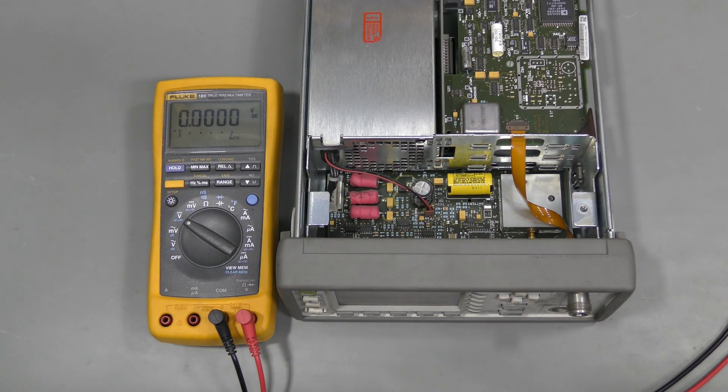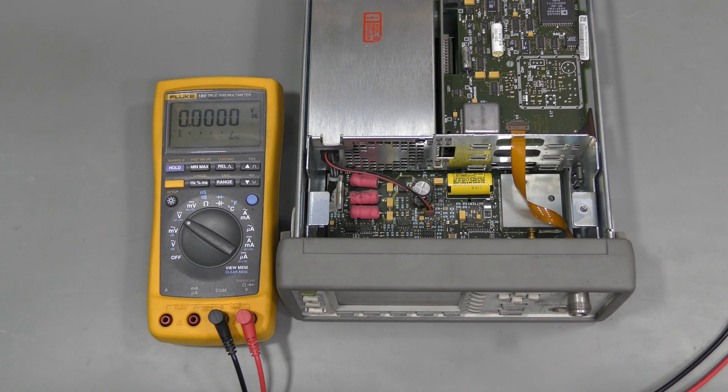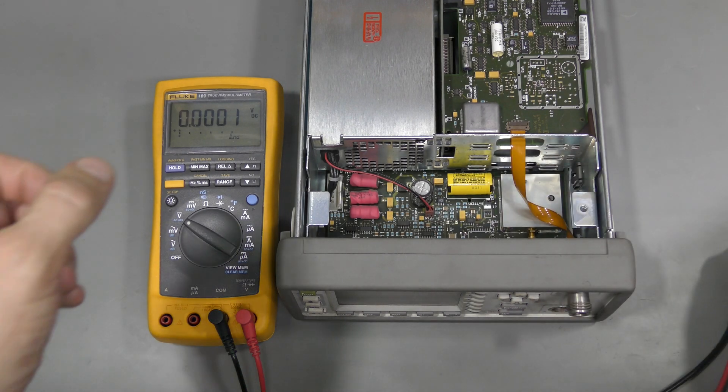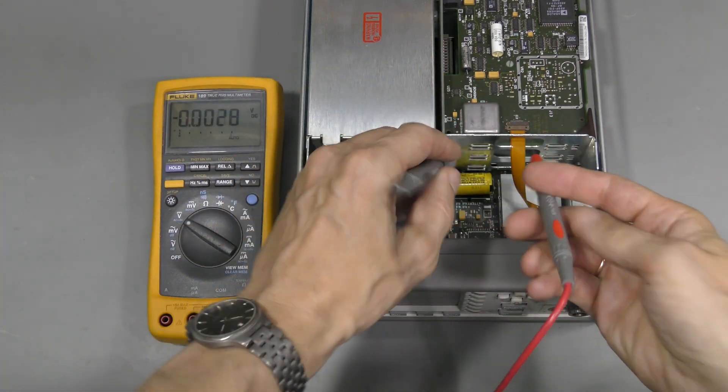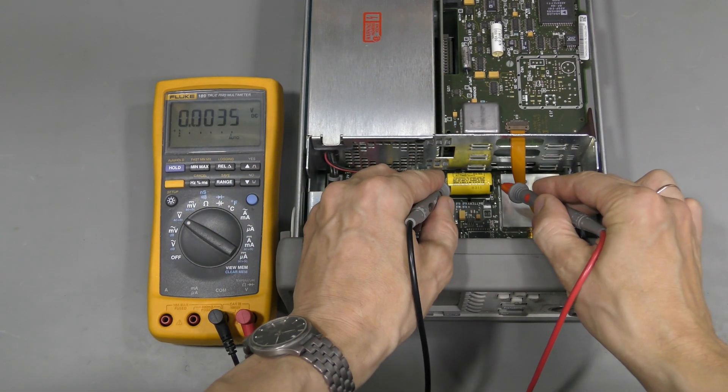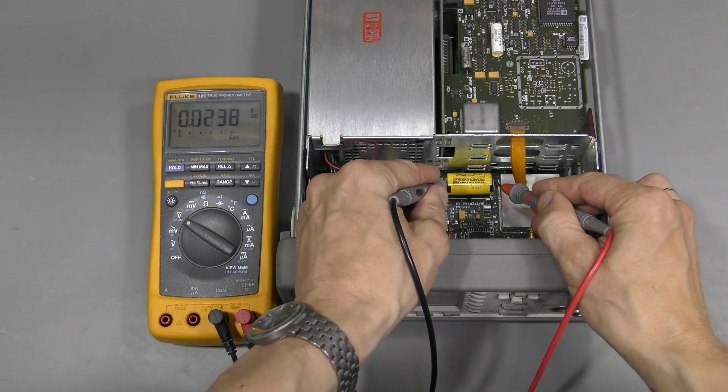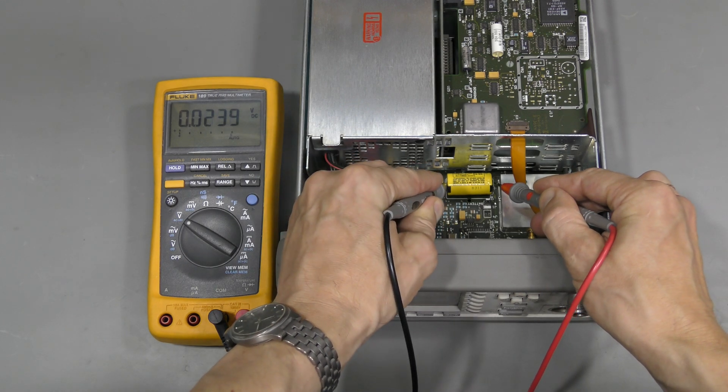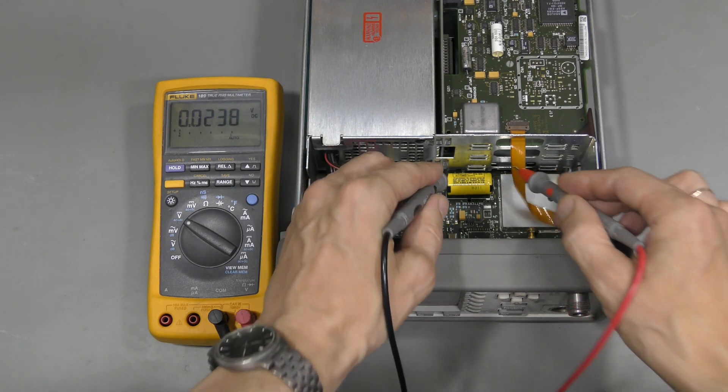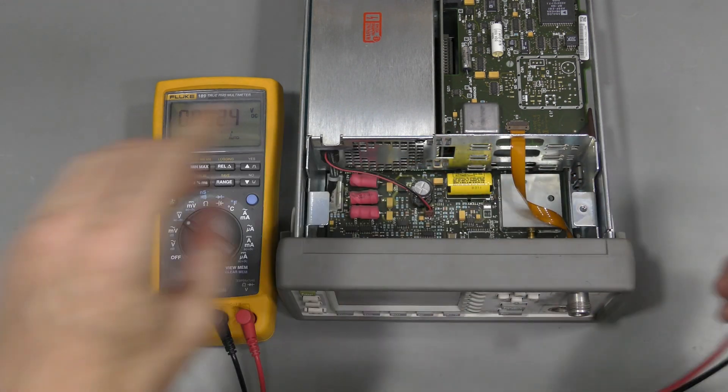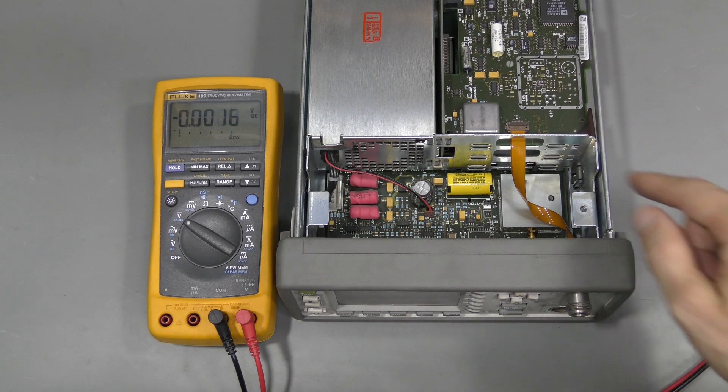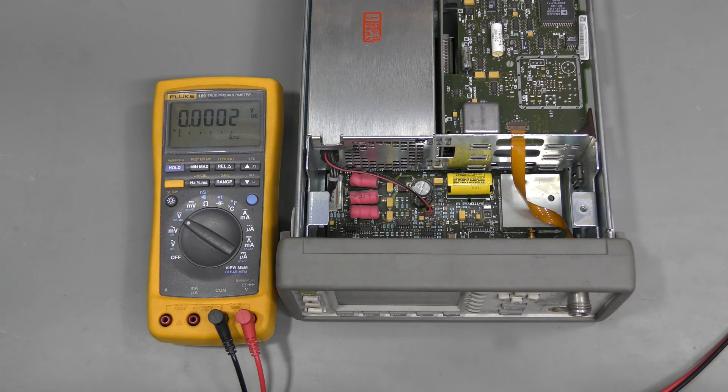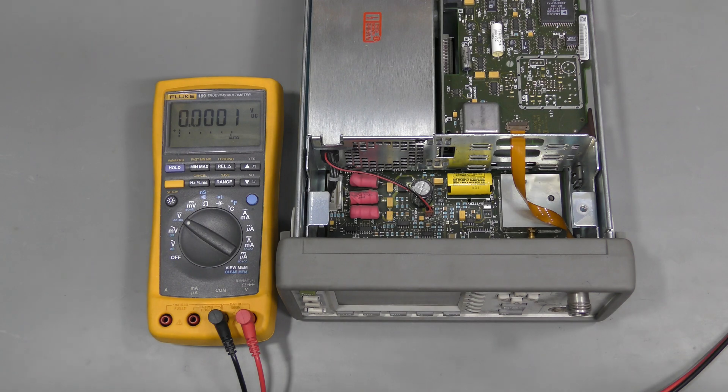I started checking and found that this lithium battery is dead. Almost zero volts. So I think we should replace it first before doing anything else. It might be the reason the meter does not start up.